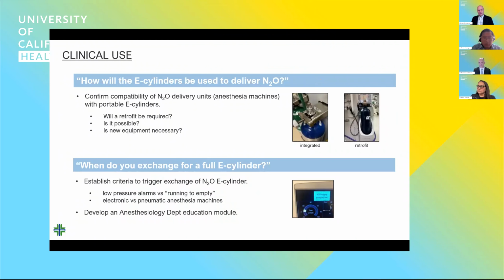Making sure that the e-cylinders are compatible with the delivery units. This can be variable. The images there on the right. Some of our anesthesia machines come with a yoke, an attachment yoke for e-cylinders already. Those are easy. You just attach one on there. The machines in the image on the far right, those can require a retrofit, which can represent an expense for your hospital to get that done. And it's important to get a sense of that early on.